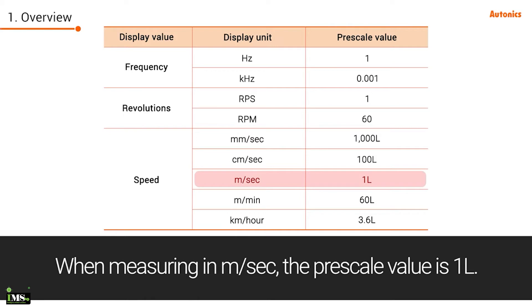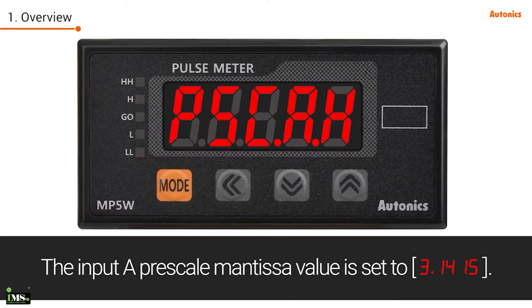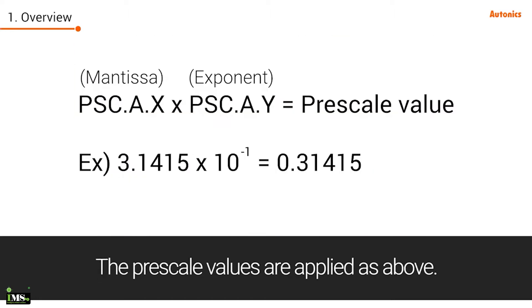When measuring in meters per second, the prescale value is 1 times L. The calculation method is as shown. The input A prescale mantissa value is set to 3.1415, and the exponent value is set to 10 to the power of minus 1. The prescale values are applied as above.